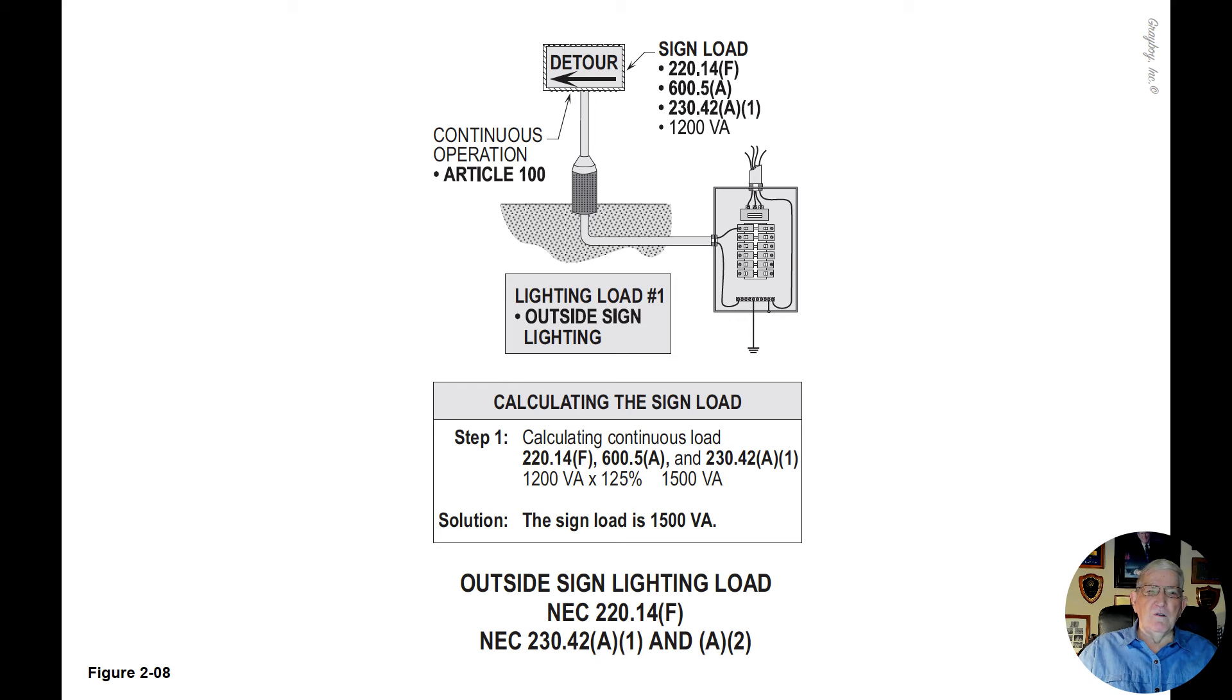Notice that basically 600.5 along with 220.14F working together would require a 20 amp circuit brought to the front of a facility where you had direct access by a pedestrian.